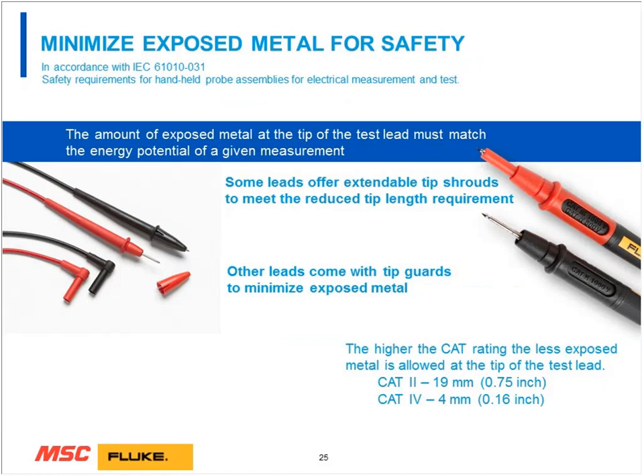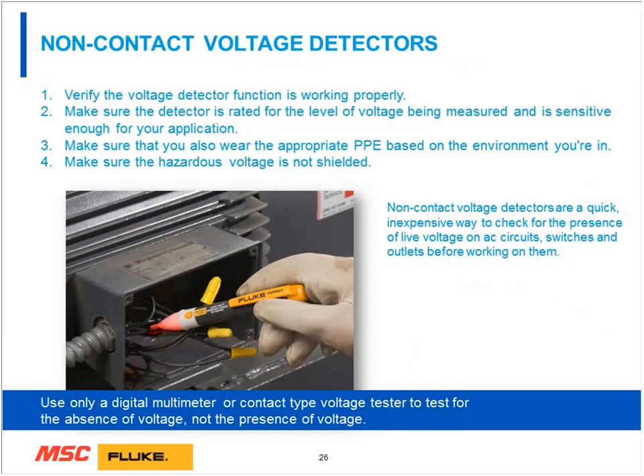Minimize exposed metal for safety. We talked a little bit about this. In the Category 4 environment, you can only have 4 millimeters, that's 0.16 inches of exposed metal. In a Category 2 environment, which is for the receptacle, that can be up to that 3/4 of an inch. Now, we have some special test probes. That's the TL175s that you can see in the picture. That actually rotates a guard that comes into place that's built into the test leads. Or you can use just some simple test lead probe insulators that you'll see on the left, and that you should definitely use in a Category 4 environment.